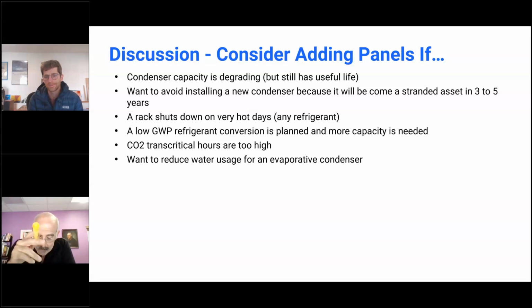Okay, and so this payback you're talking about, the 3 to 7 years, is not about capex and replacing condensers. That's just energy savings alone. Is that correct? Yes, and it's going to depend on the cost of electricity and the details of the cooling system. Oh, absolutely. So we were just talking about LA, where power is what, 25 cents more or less, 22 to 25. I would say with that, it's assuming that these are persistent cooling loads. This is not going to be building HVAC for an office, where you don't run a compressor that often, but this would be a supermarket, or a data center, or a cold storage facility. And this would be strictly for HFC systems.